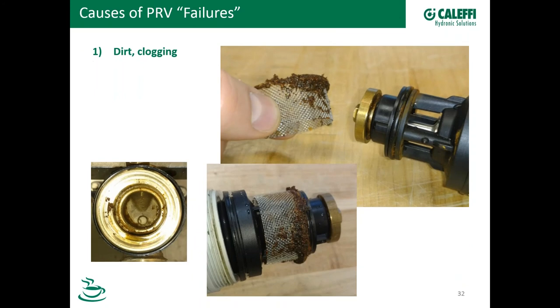The screen caught most of it, but look at the seat inside — you can see deposits around the seat. This is where the valve seals, and because there are little particulates and impurities there, pressure is going to leak through. Dirt is a major factor — that's why you want isolation valves and a regular maintenance program. All pressure-reducing valve manufacturers offer some sort of screen in their PRV to protect against this, and some plumbers practice redundancy by including a straining device upstream from the PRV for that double layer of protection. In some codes, if the valve is smaller than an inch and a half, you have to have a pre-filter.